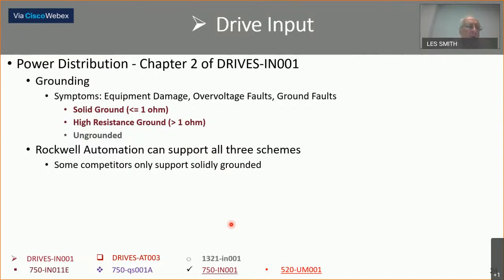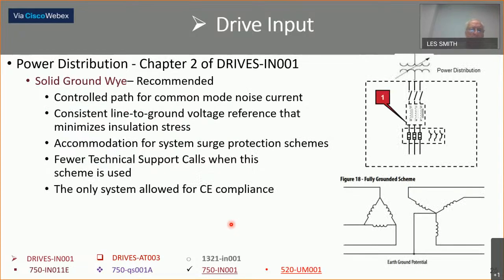Again, here we go, grounding as stated: solid ground less than 1, high resistance ground greater than 1, or ungrounded. And the drives can go with either grounded or ungrounded. You just have to arrange the jumpers per the literature. Here we're just going to look quickly at the types. Here we have a grounded Y, and the statement here is only system allowed for CE compliance. You're not CE compliant or you're not UL compliant unless you have a grounded system.